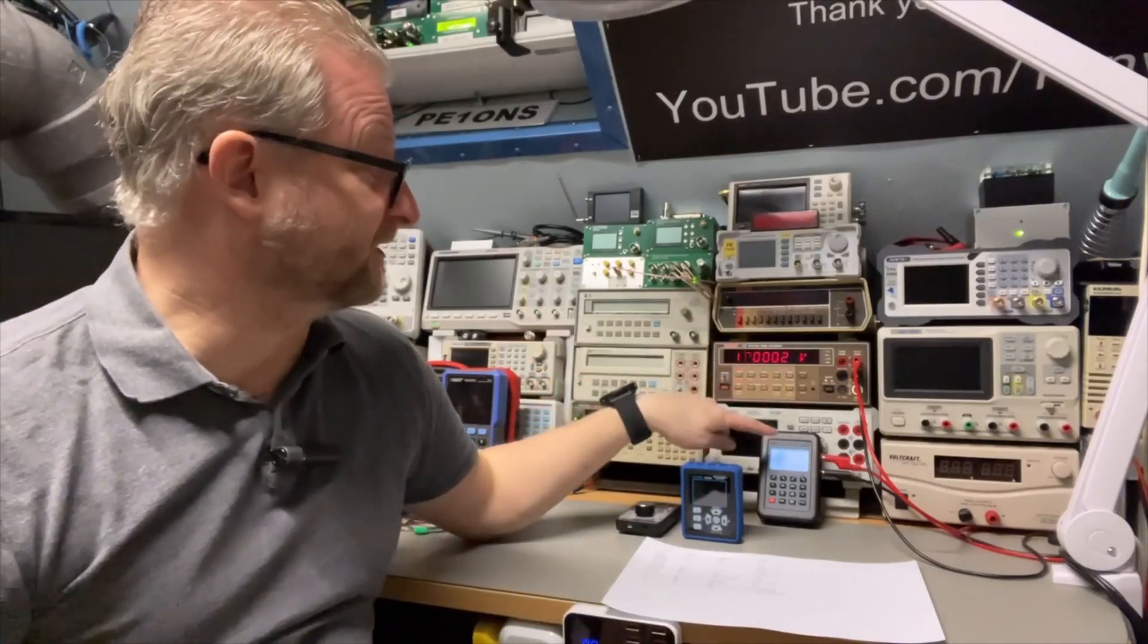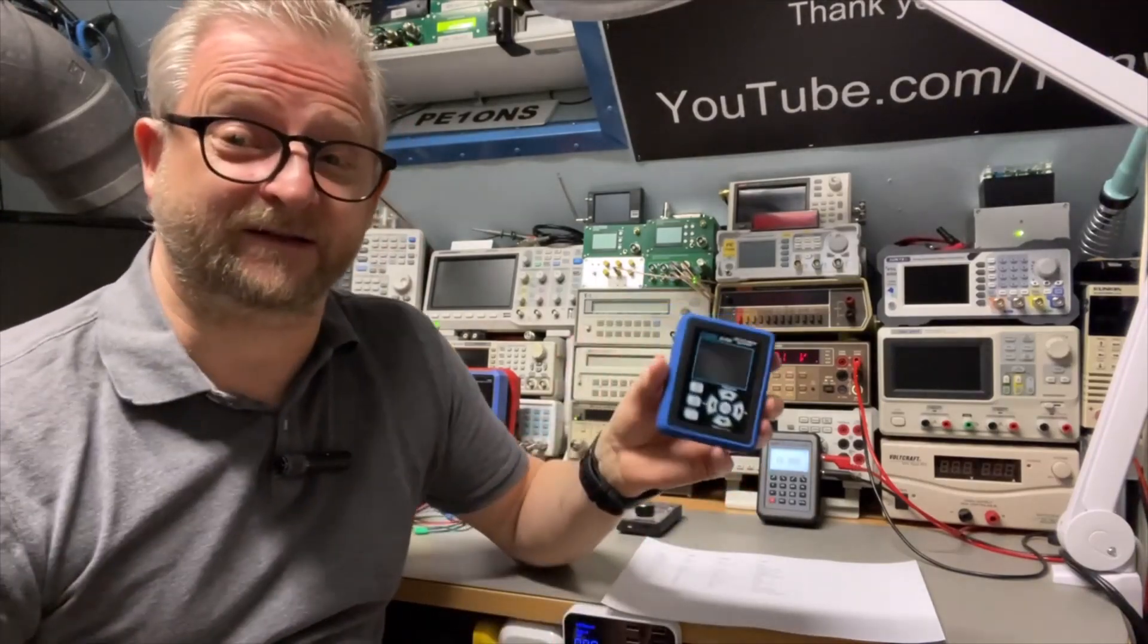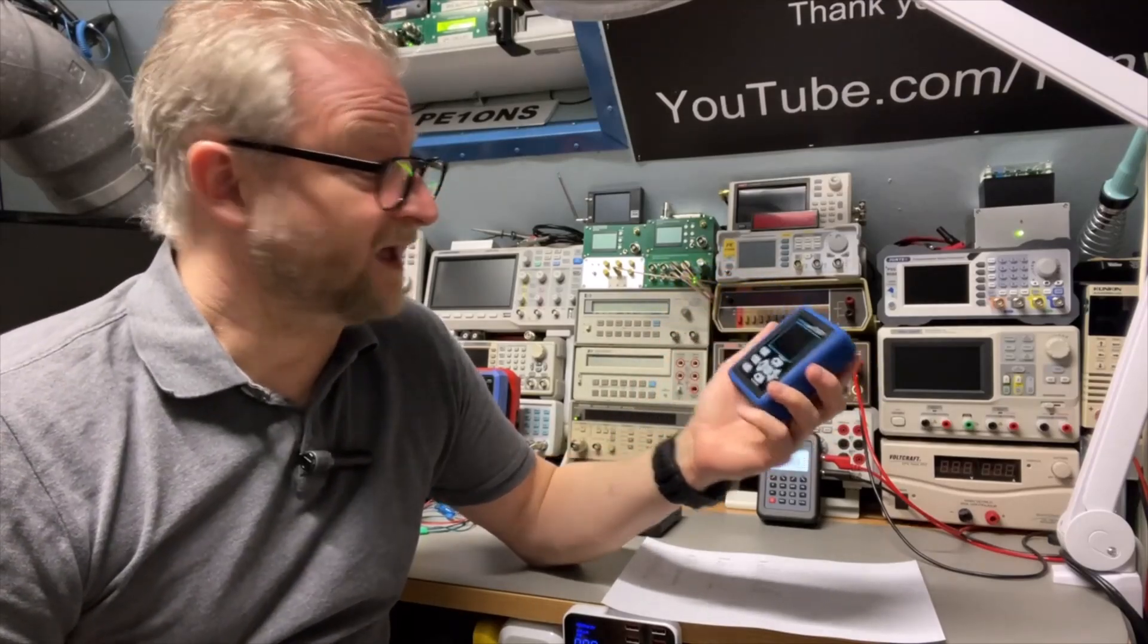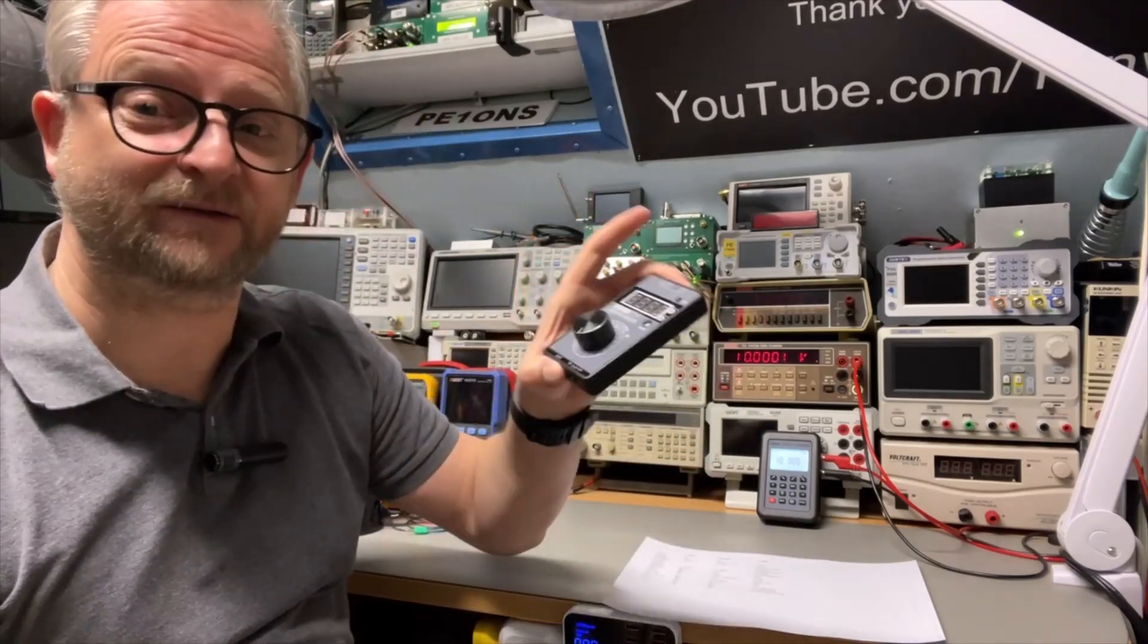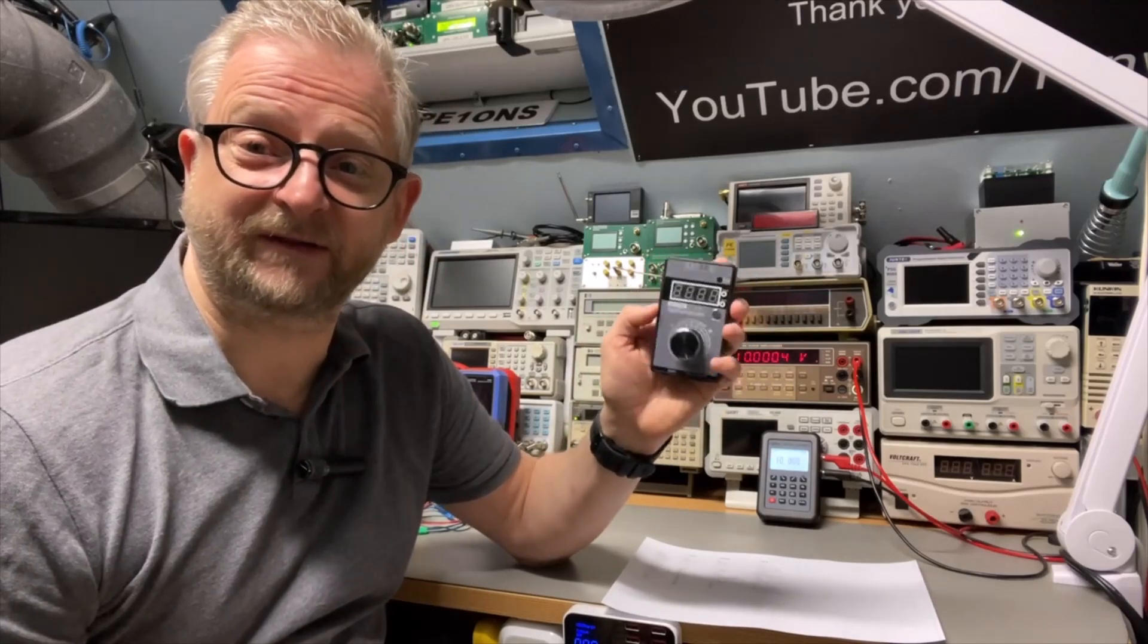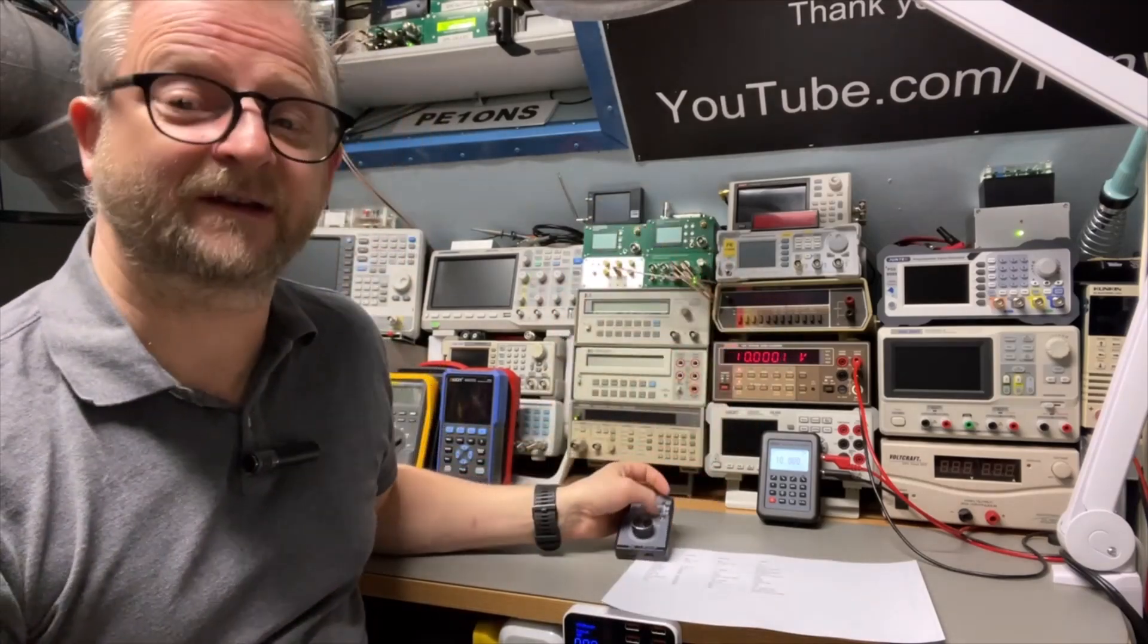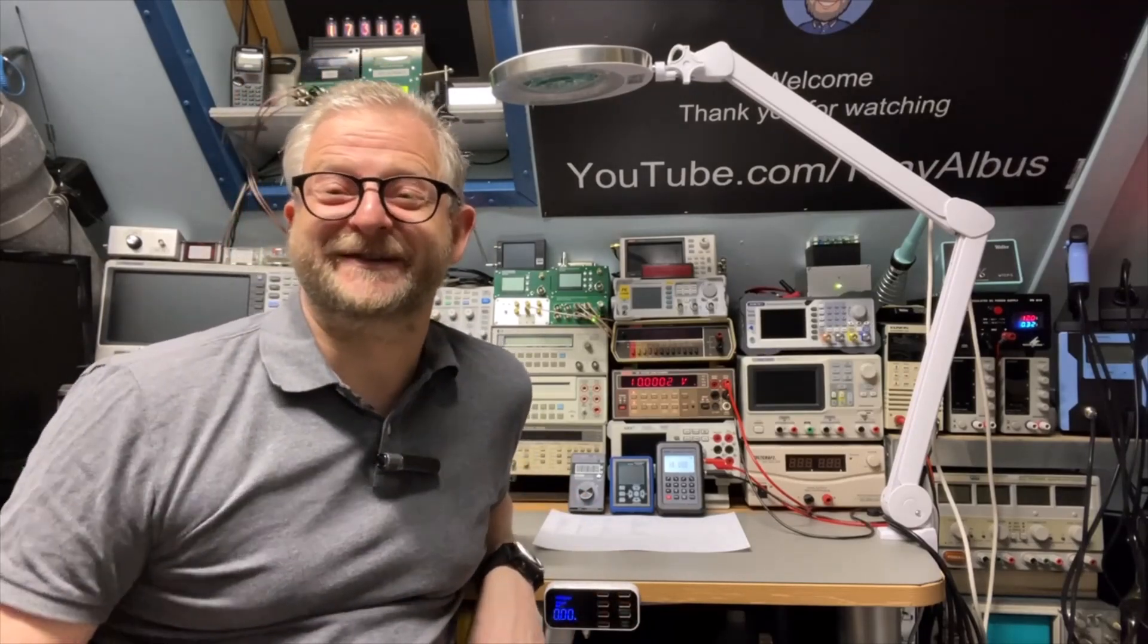It's probably clear which one is my favorite - I really like the LB02A and it is really calibrated proper. But it doesn't mean that the FNIRSI is not good. For its price like 45 euros, they made a nice calibrator, especially when you compare it to this one which is super basic and uncalibrated. What's the use of a calibrator if it is not calibrated itself? But you can do simple checks just to see if something works or not. So that was my five minutes on process calibrators. Thank you for watching and I hope to see you next time.